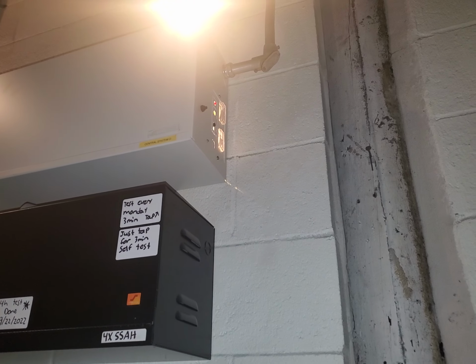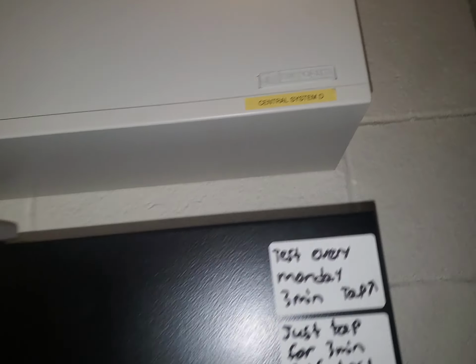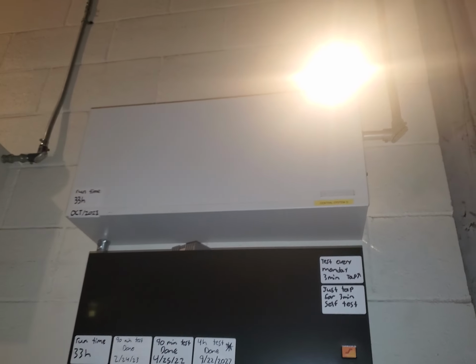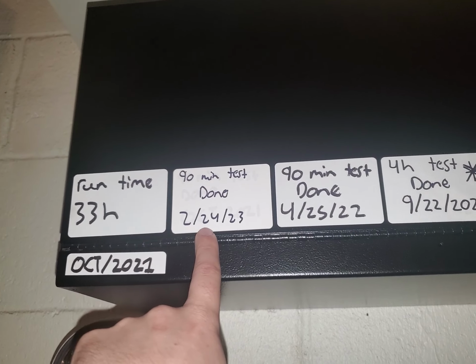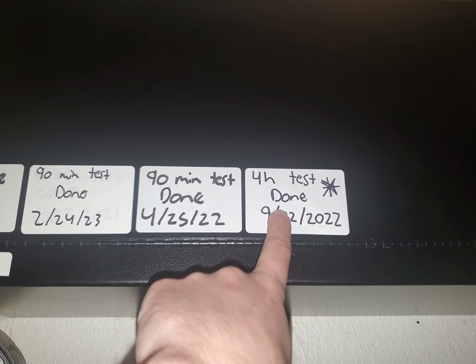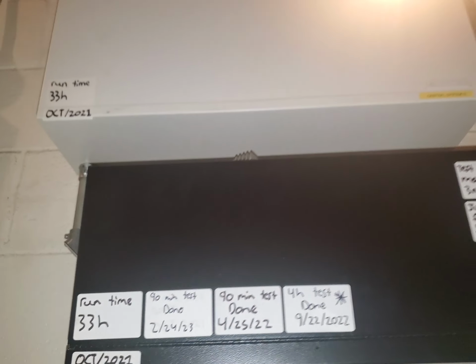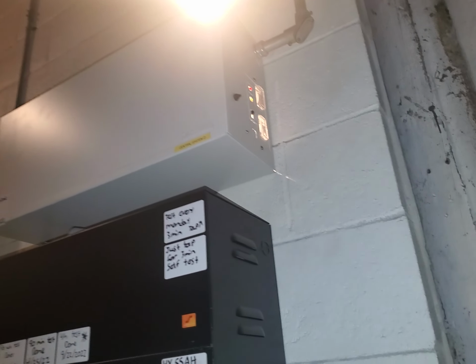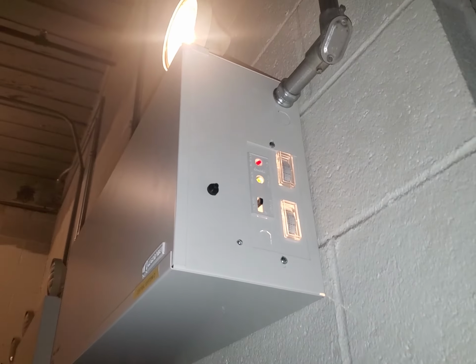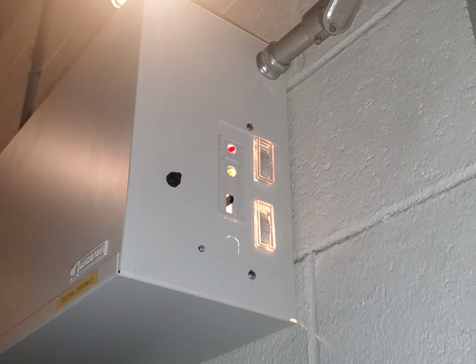So today, we're doing a video on Central System D. This is Central System D. And as you can see, what sets it apart from the others is it has a runtime of 33 hours. Here's our test records. That was our 4-hour test. It lasts 33 hours. As you can see, it has lighted voltmeters. Those voltmeters are lighted. I'm going to zoom in on them so I can read the readings later.